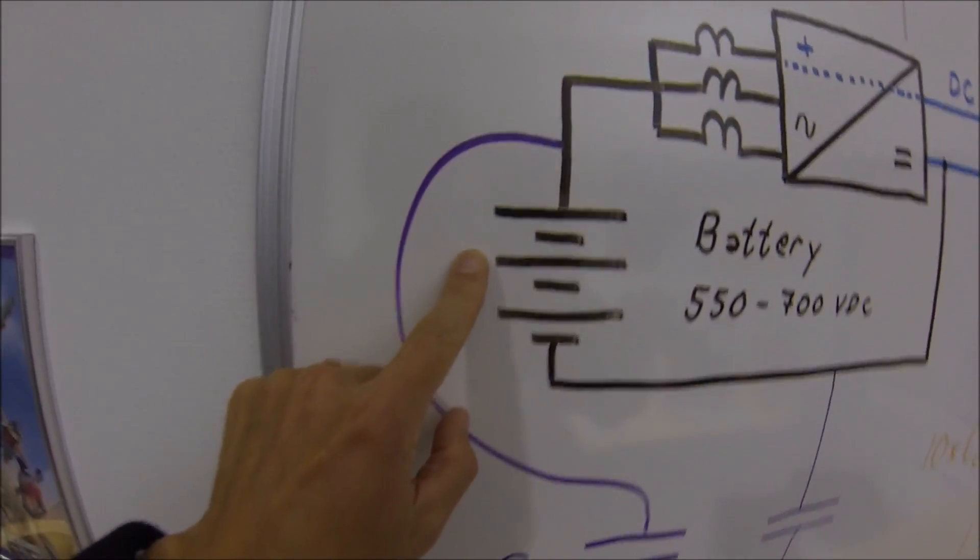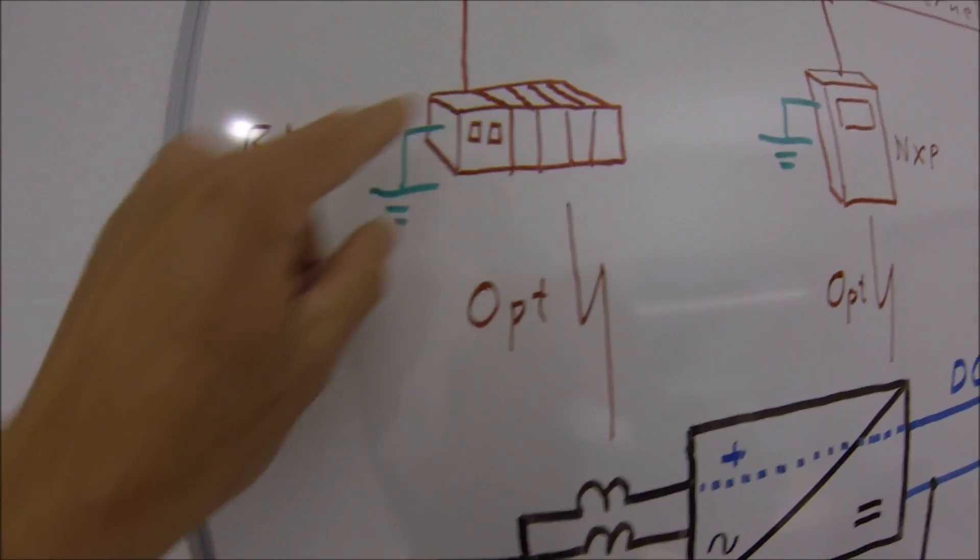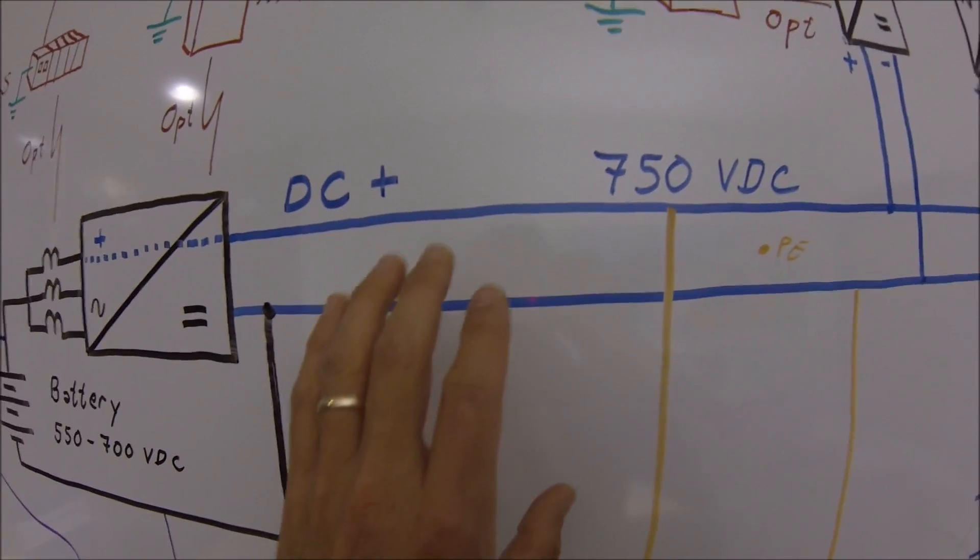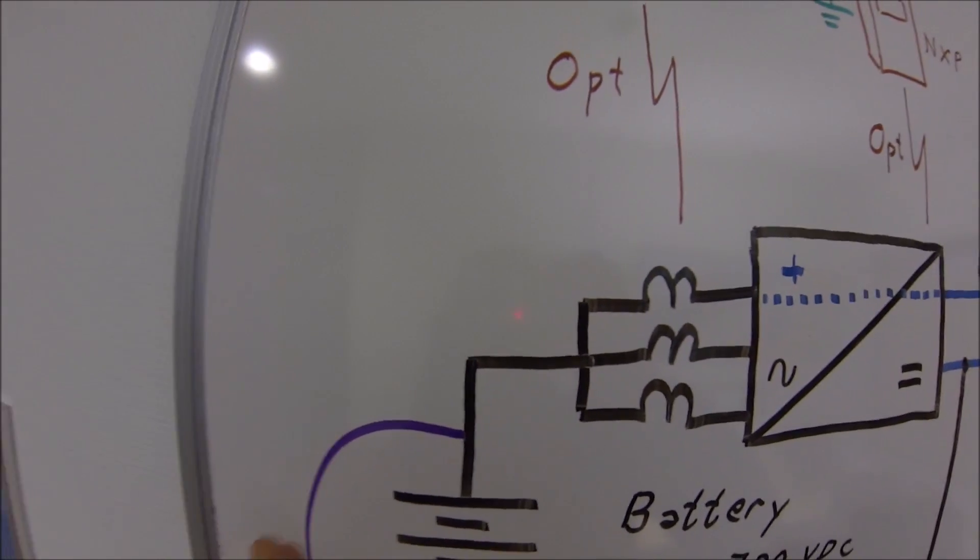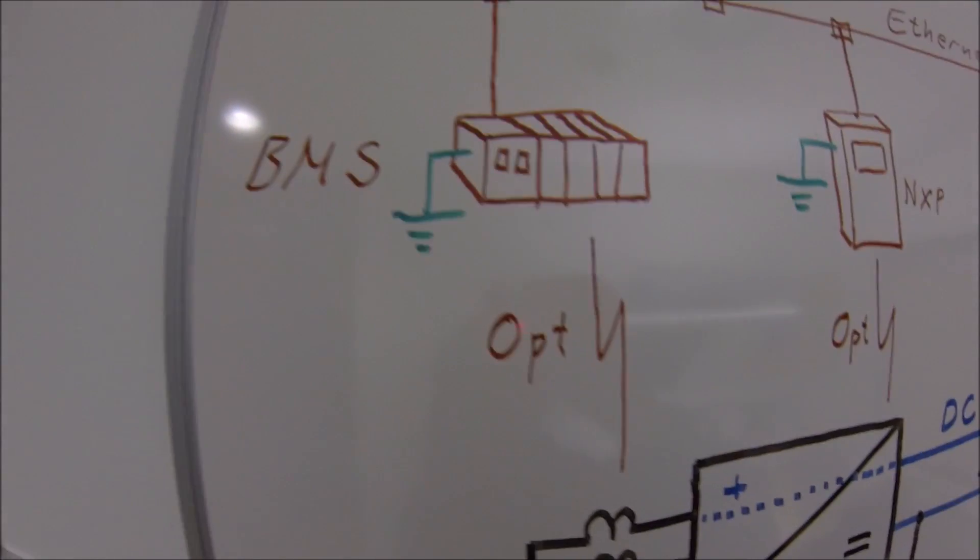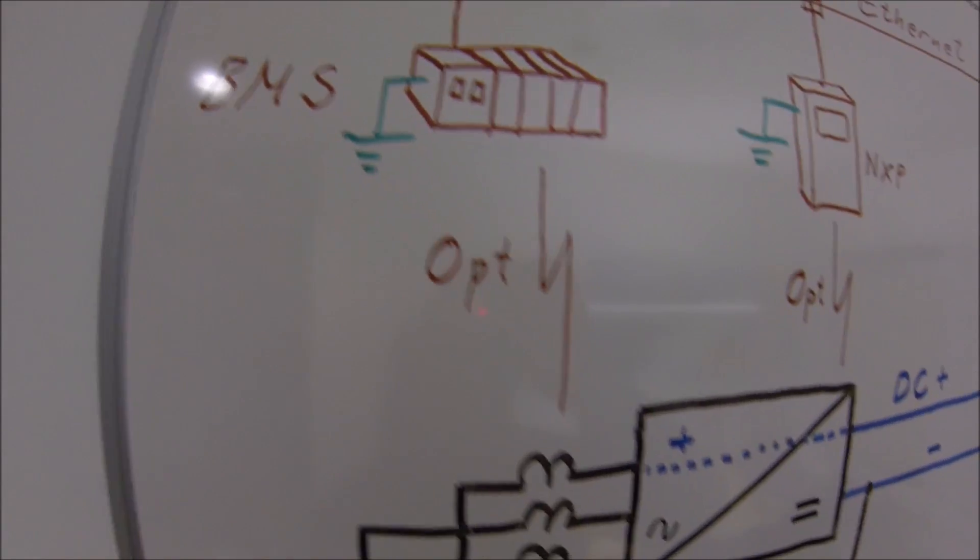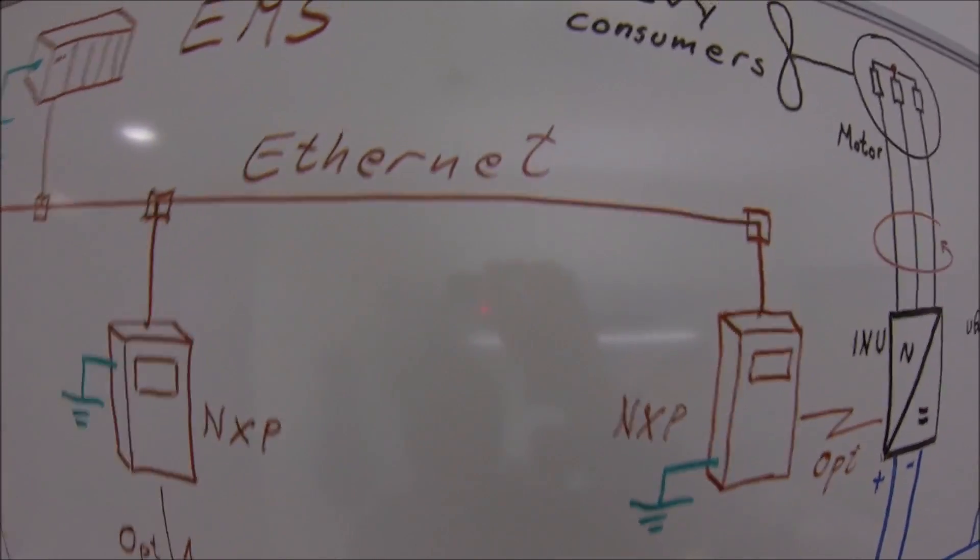Because if you have a galvanic connection to here, well, you in practice have ballasted your DC bus here instead of here. And of course, then you will have currents going on here which disturb the communication system. Same is with the Ethernet and field buses.